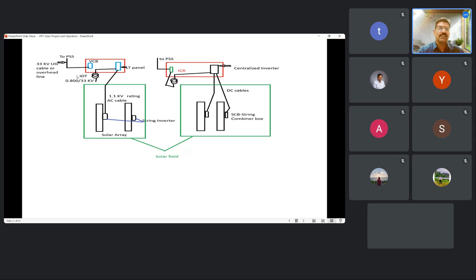PPC, power plant controller, as told earlier, now BESS is also introduced. So whether it's the solar plant inverter itself, the WTG, or BESS, all have their own energy management system. Other components are for reactive power compensation, capacitive or inductive, STATCOM or SVG may come. All four parts will be integrated with the PPC, power plant controller, which takes it to the grid.